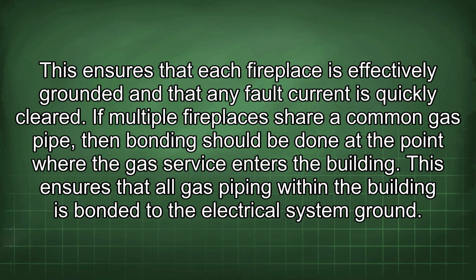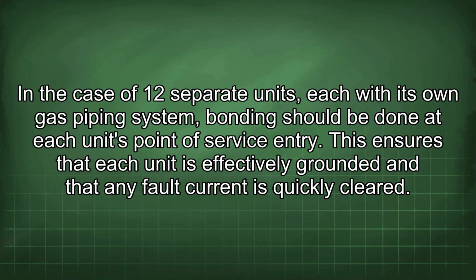If multiple fireplaces share a common gas pipe, then bonding should be done at the point where the gas service enters the building. This ensures that all gas piping within the building is bonded to the electrical system ground. In the case of 12 separate units, each with its own gas piping system, bonding should be done at each unit's point of service entry. This ensures that each unit is effectively grounded and that any fault current is quickly cleared.